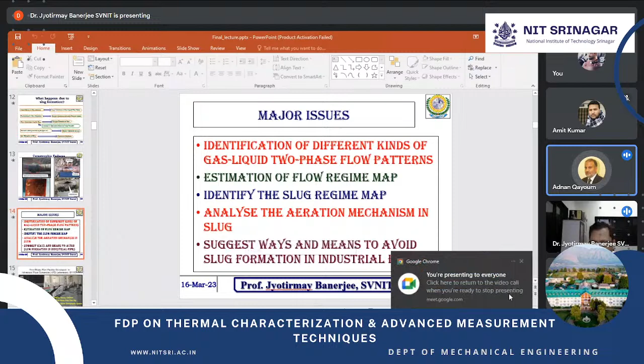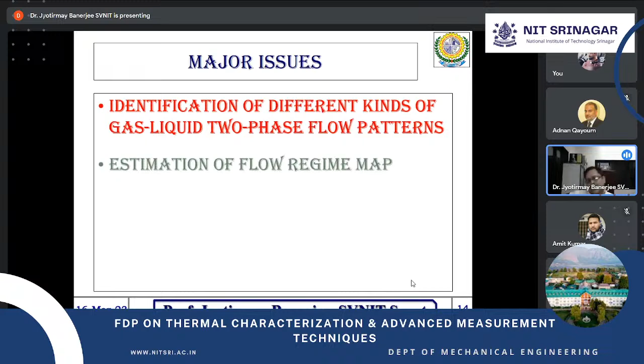The major issue that was there in our mind while we took up this research was, first, to identify all kinds of patterns that can happen in gas-liquid two-phase flow, and then create a flow regime map. So I wanted to know what flow rates we must operate individually for the gas and for the liquid. Because the accident that happened in GIPCL was because the person operating the control valve operated it much faster than expected, which allowed a larger mass flow rate of the gas to flow over the liquid, creating a sudden wave that rose and blocked the passage.